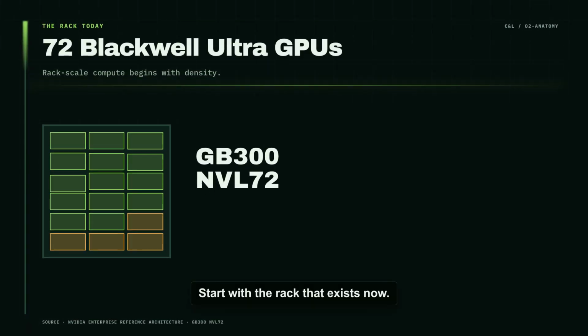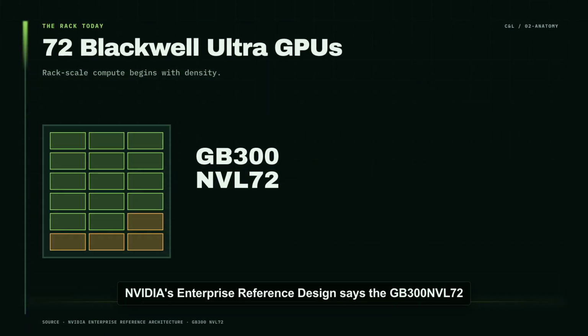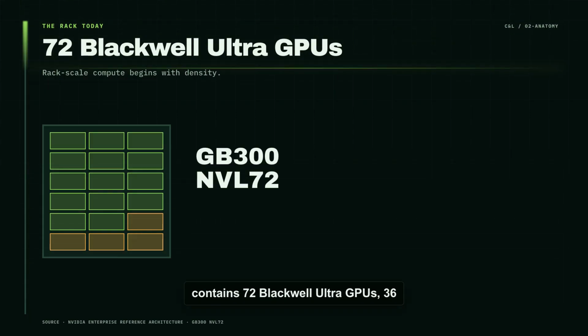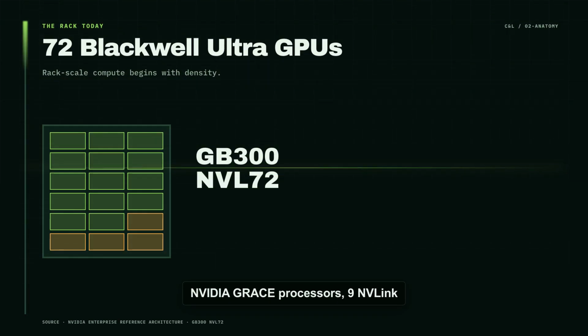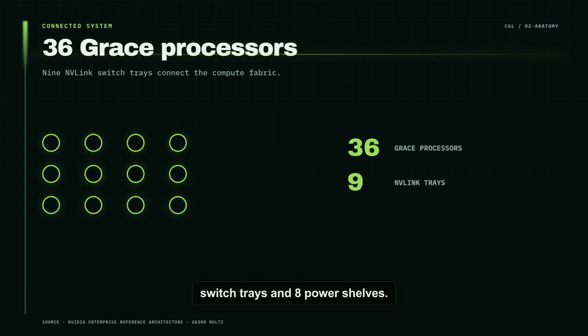Start with the rack that exists now. NVIDIA's enterprise reference design says the GB300 NVL72 contains 72 Blackwell Ultra GPUs, 36 NVIDIA Grace processors, 9 NVLink switch trays, and 8 power shelves. The full rack can require up to 142 kilowatts, and it is liquid-cooled.